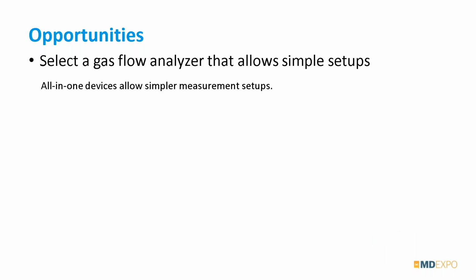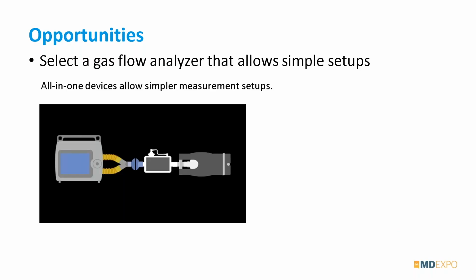A lot of times now we're seeing the all-in-one devices. This means it's pretty simple. You can connect the patient circuit to one side and a test lung to the other, and all the parameters that you need to measure are done through its main flow channel. So you don't have to tee in oxygen, you don't have to tee in pressures, you don't have to add a trigger cable, things like that. So knowing your system, getting one that's simple, all these things go to help minimize the risk of measurement errors that are caused by these setups that are inappropriate or complex.